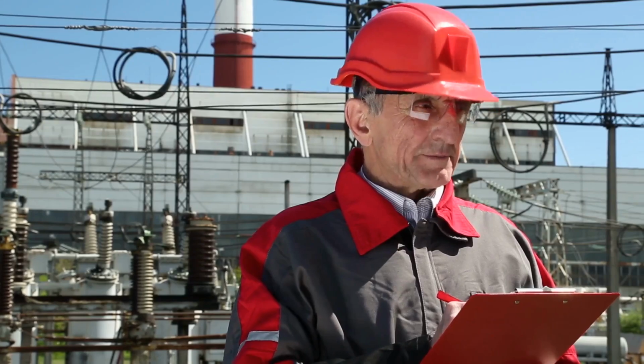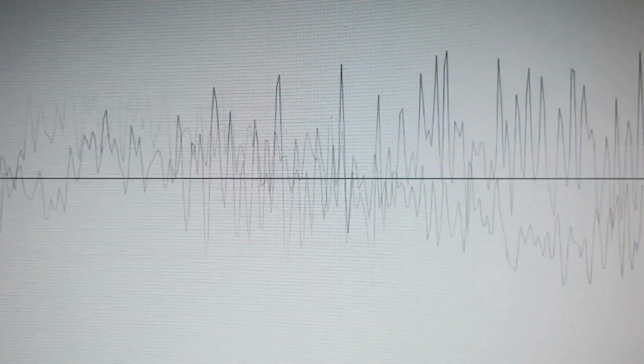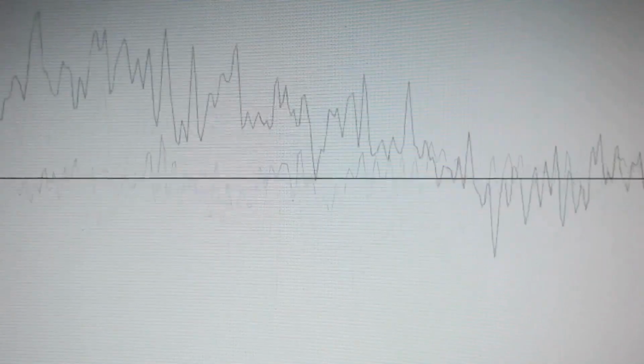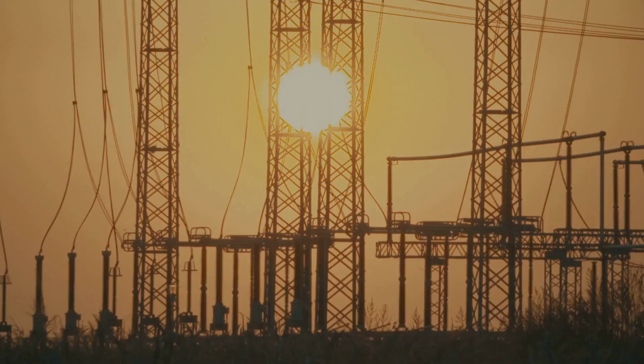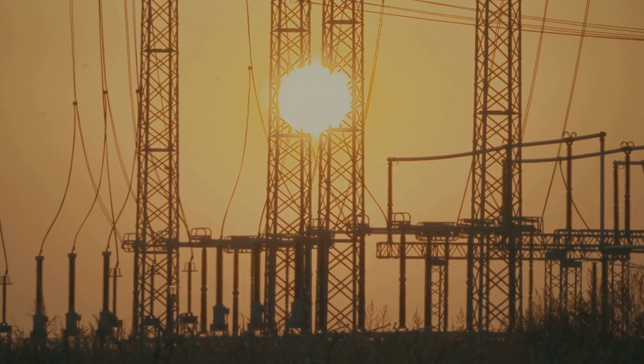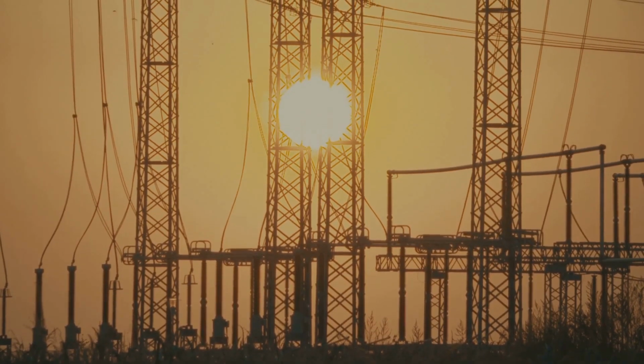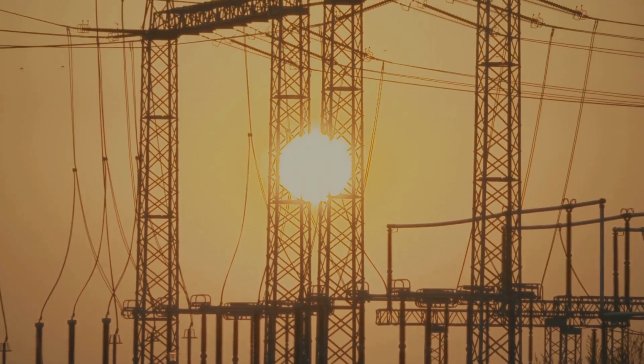Clause 6.2. Frequency ride-through. Similar to voltage ride-through, frequency ride-through curves define acceptable high and low frequency thresholds and durations. Low frequency ride-through, LFRT: stay connected down to 57 Hz for up to 300 seconds. High frequency ride-through, HFRT: stay connected up to 62 Hz for at least 300 seconds. This ensures DERs contribute to inertia-like support, reducing the risk of wide area blackouts during frequency instability.